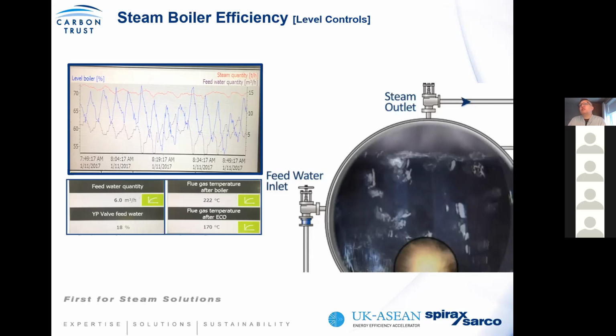Even though when you look at the steam profile, it is roughly about 15 tons. So although the steam profile didn't change significantly, what we found is that the subtle changes in the steam pressure cause this swell condition. Where you have single element control, the swell condition forces the boiler to think it's full and stops adding water at a point in time when there's increased steam demand. And if you don't add water to the boiler, you don't get the efficiency of the economizer, for example.